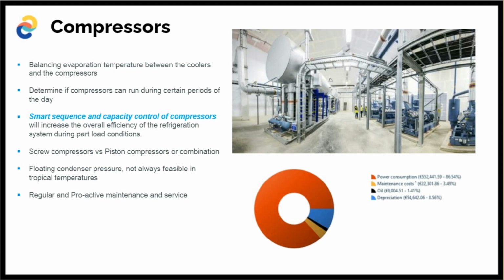And what are we going to select? Are we going to use screw compressors for big installations? Yeah, we're looking at an installation typically between 1,500 and 3,000 kilowatts. Or do we need a nice combination of piston compressors and screw compressors? What's done here in Europe a lot is a floating condenser pressure. But in the Philippines, that's not going to bring a lot.